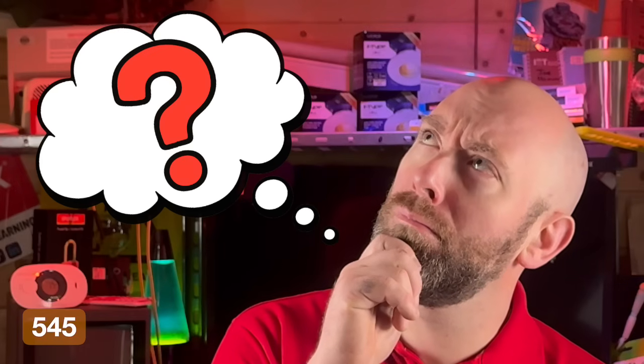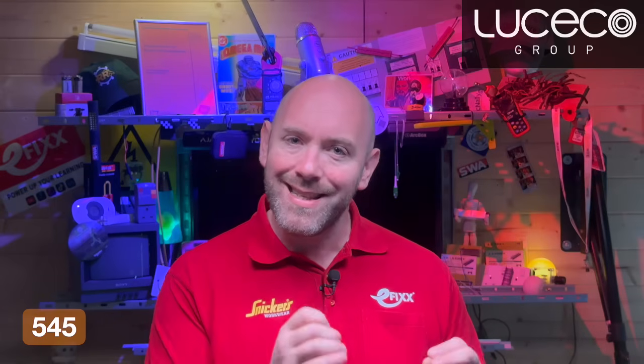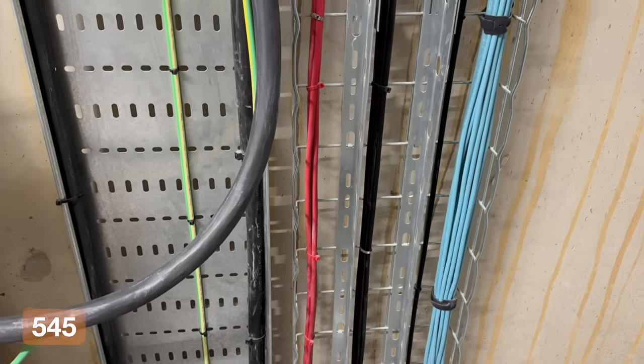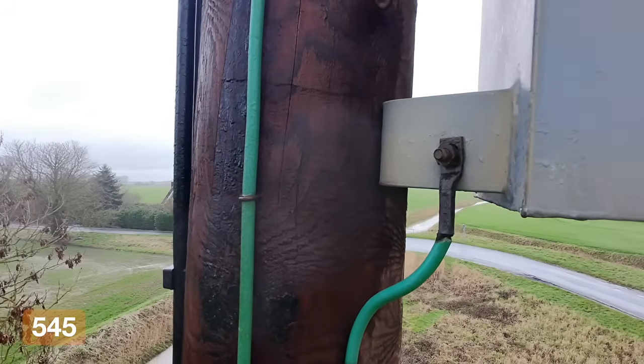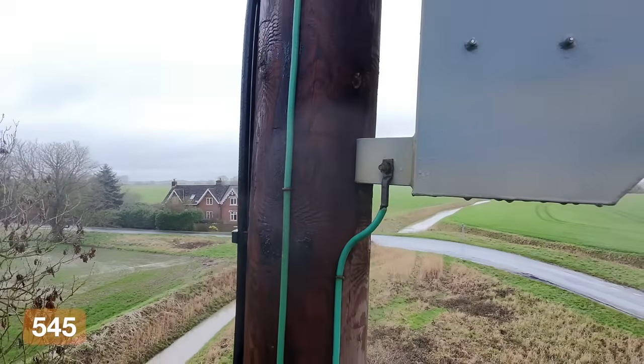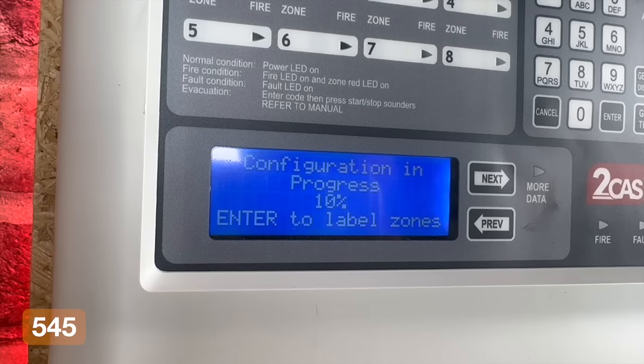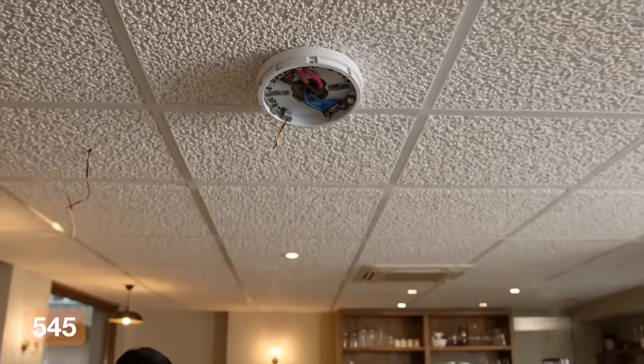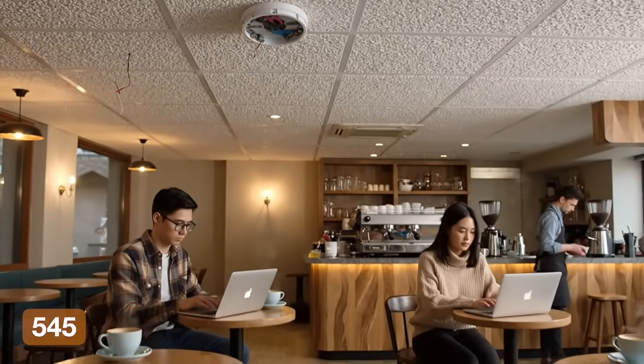Functional earthing is now formally set out in BS 7671 under section 545. This is not something new to the industry, but it has not previously been defined this clearly within the regulations. The first thing this section does is separate functional earthing from protective earthing. Protective earthing is there for safety. It is there to protect against electric shock under fault conditions. Functional earthing is different. It is there to ensure equipment operates correctly. Things like reducing electromagnetic interference, maintaining signal stability, and controlling electrical noise.